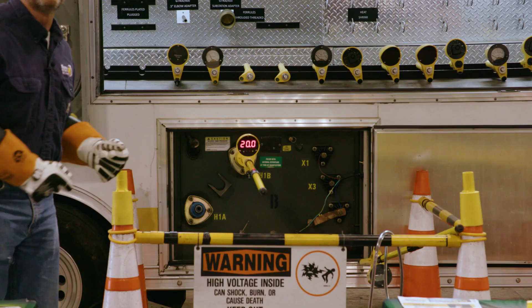So our tools are designed to make direct contact with the X. We're getting about 20,000 volts, a pretty accurate tool. When you're using your tools, you always want to use them on a live known voltage source prior to use, to make sure the tool is functioning and calibrated properly. So we're using a live known voltage source before we open the switch. Remember, the battery test doesn't test the tool's functionality. So we know our tool's working pretty good, about 20,000 volts, pretty accurate.